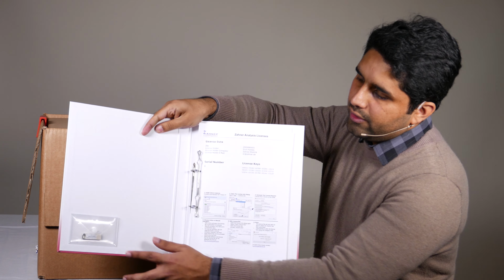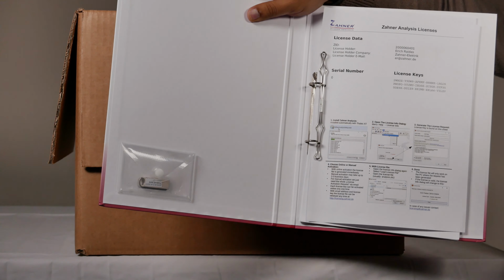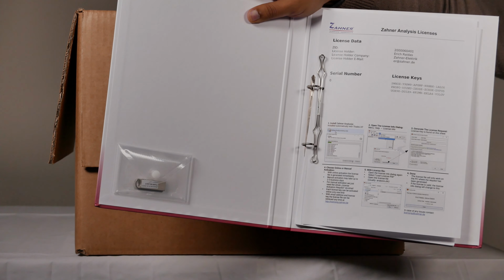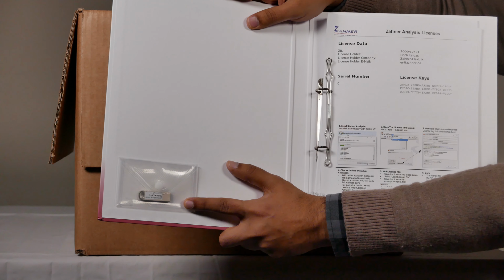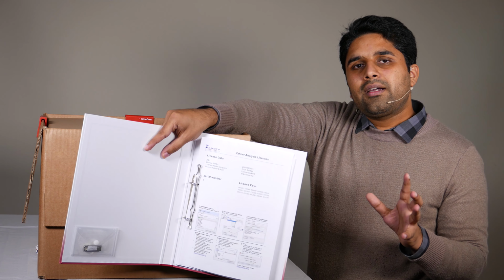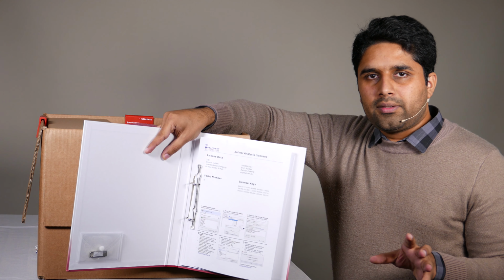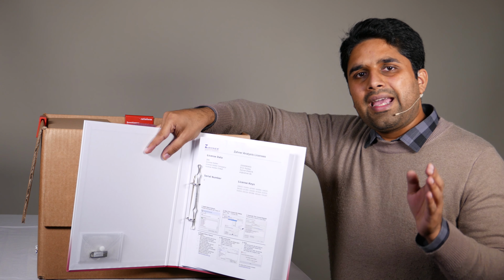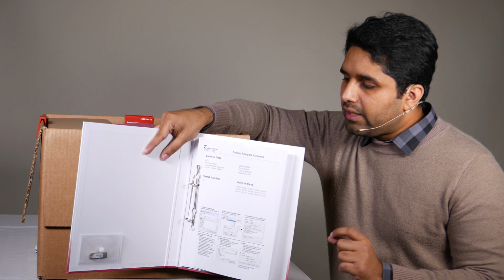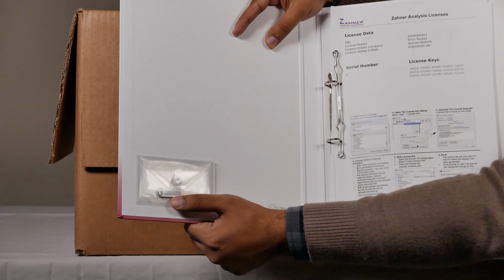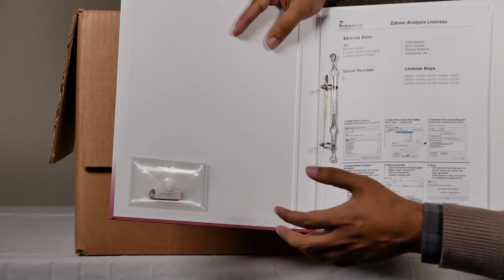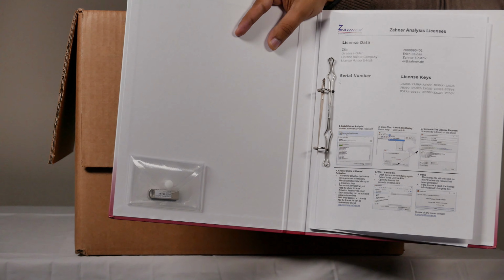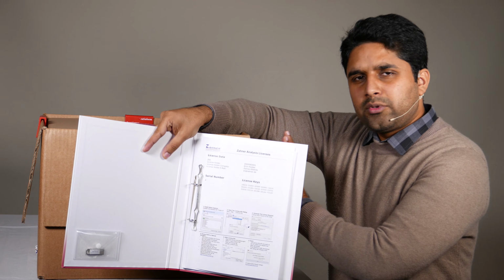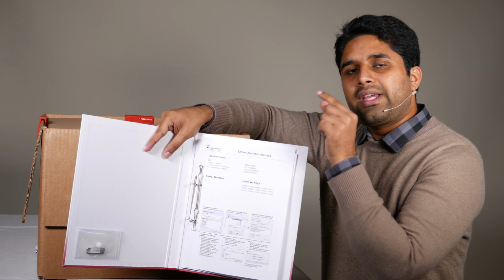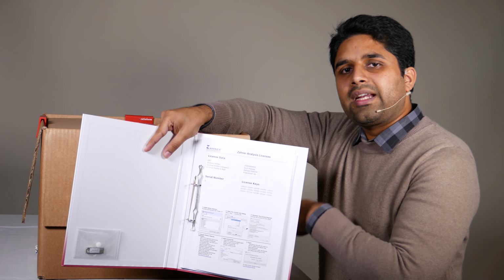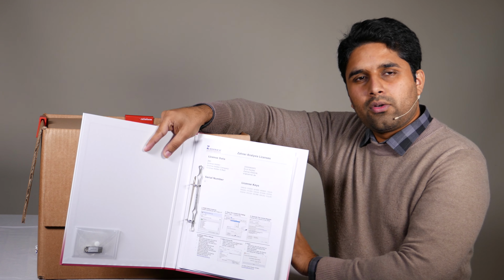At the right here we have this USB. This USB contains the latest version of the Thales software and the ZAHNER analysis software, so you can install them. In addition to that, it also has the calibration data for your device. Here in ZAHNER, each and every potentiostat is individually calibrated. That means each potentiostat has its own calibration data, and the calibration data for your device is within this USB. You can see that this USB has a small sticker, and this sticker contains the serial number of your device. The serial number is also on your potentiostat, so you can check which USB belongs to which potentiostat, and then you know that this calibration data belongs to this device.